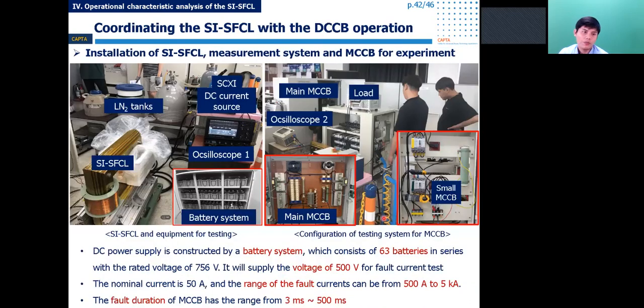For the final additional experiment, the lab scale SI-SFCL was tested in coordination with a real DC circuit breaker, a mechanical circuit breaker. The full testing system was developed and fabricated like this. The DC power supply is constructed by a battery system consisting of 63 batteries in series. It will supply the voltage of 500 volts for the fault current test. The normal current is 50 ampere. So the range of the fault current can be from 500 ampere to 5 kiloampere. The fault duration of the circuit breaker has a range from 3 millisecond to 500 millisecond.